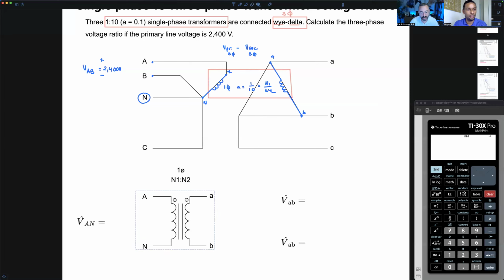So down here, this diagram is a single phase transformer - we're looking at the single phase transformer in this red box from capital A to capital neutral on the primary, and from lowercase a to lowercase b on the secondary. This transformer is just one of the individual single phase transformers out of the three total that make up this three phase Y-delta transformer. Does that make sense? Yes, it does.